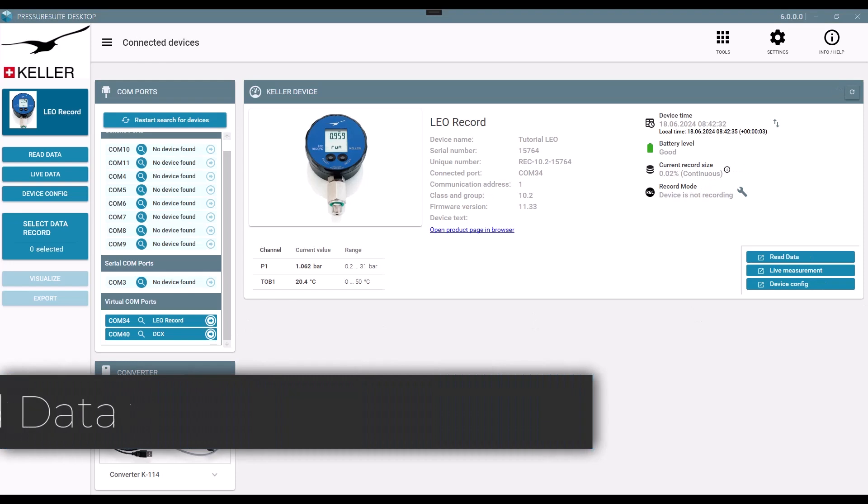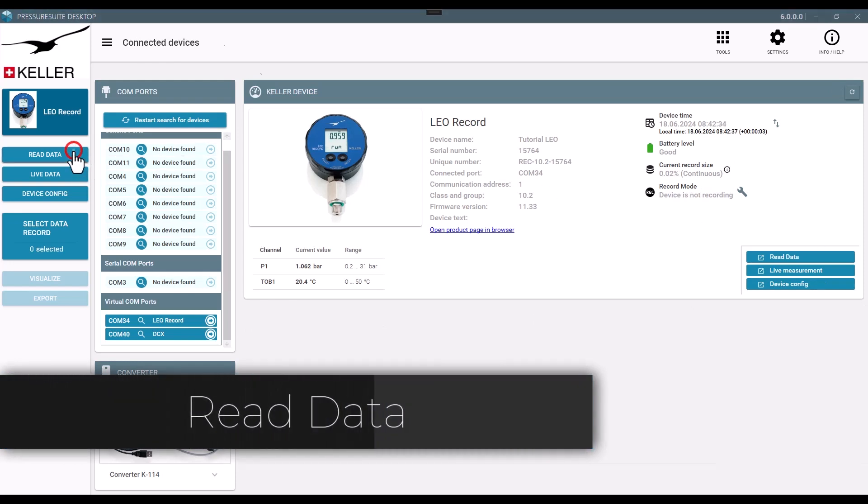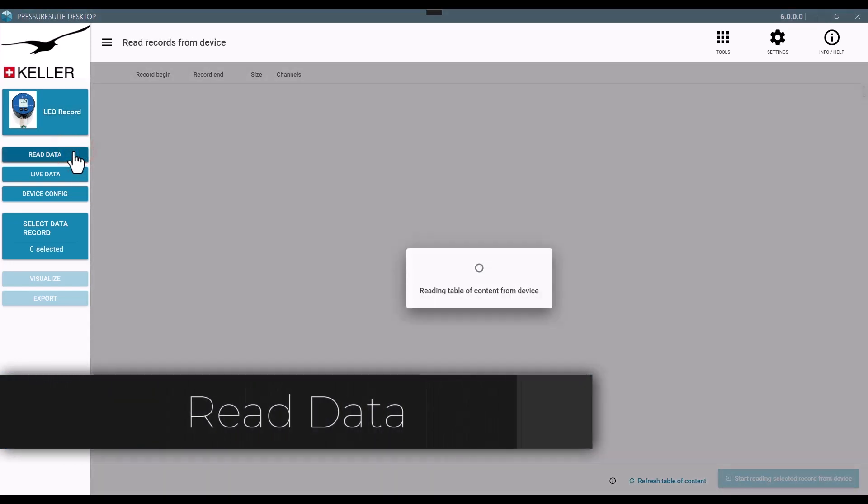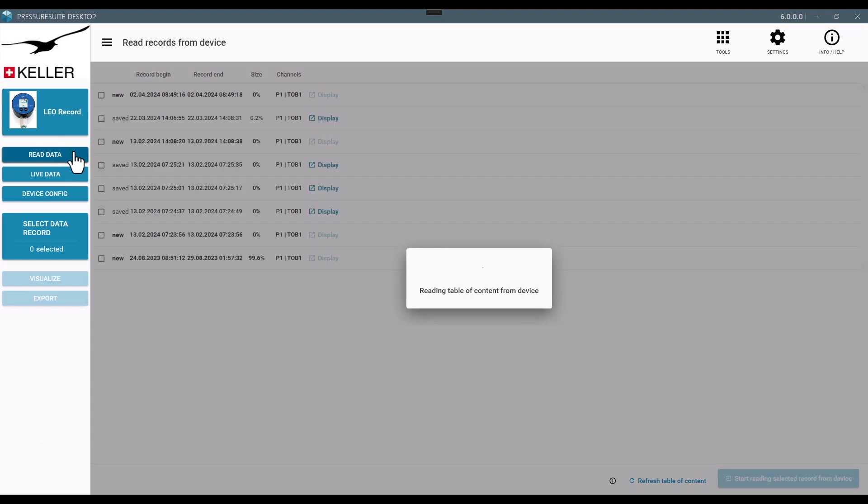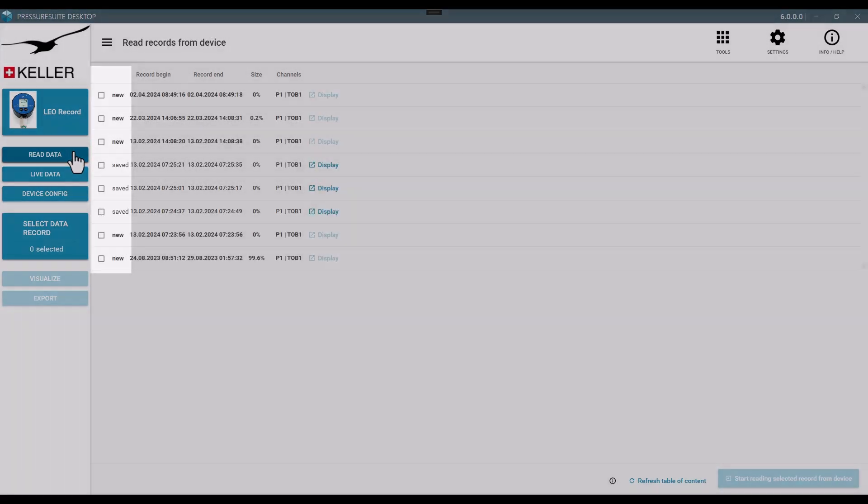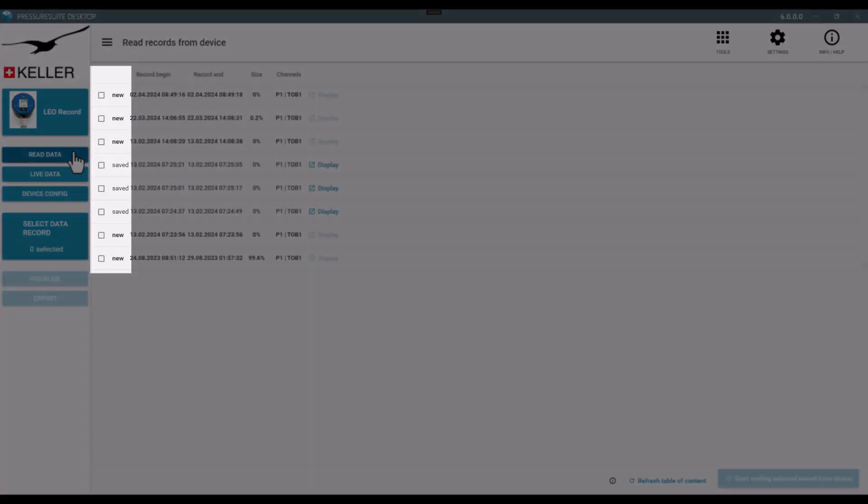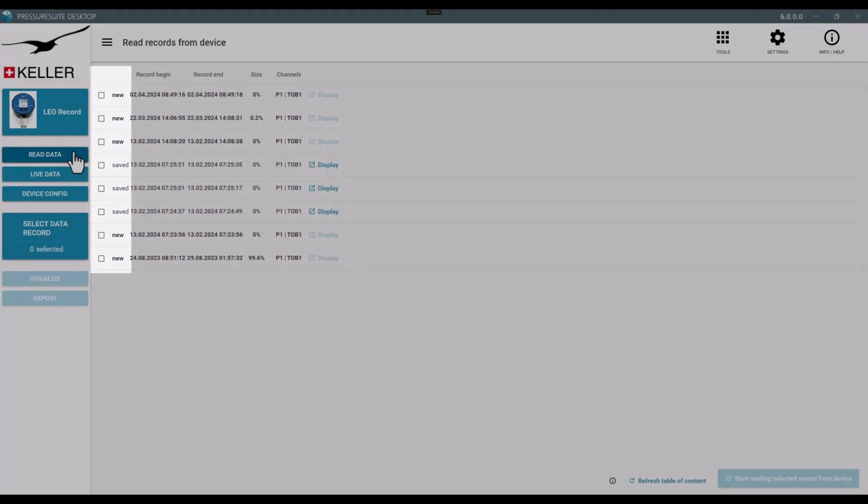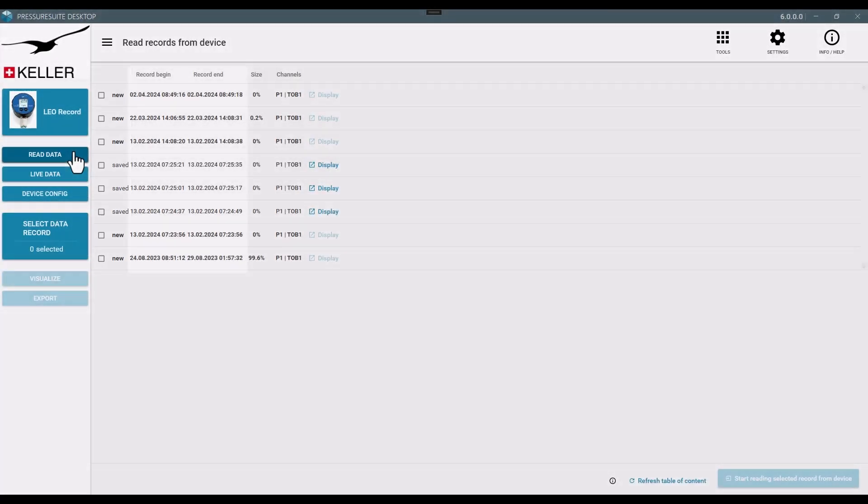Press Read Data and Pressure Suite Desktop reads the table of contents from the device and lists every set of measurement stored in the device as New and the ones already stored on the computer as Saved.